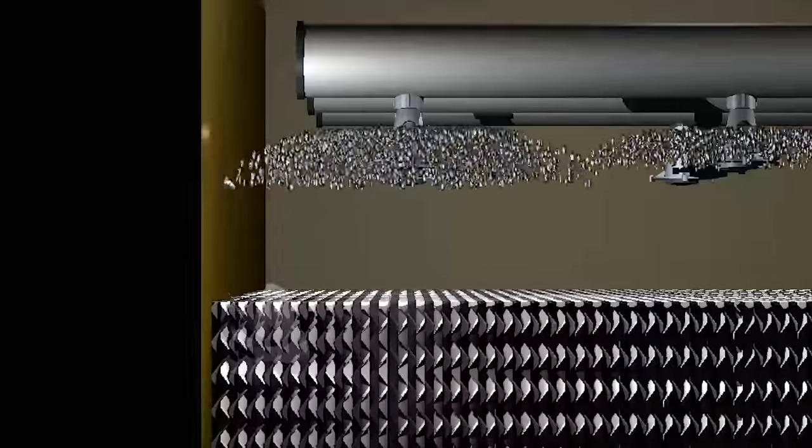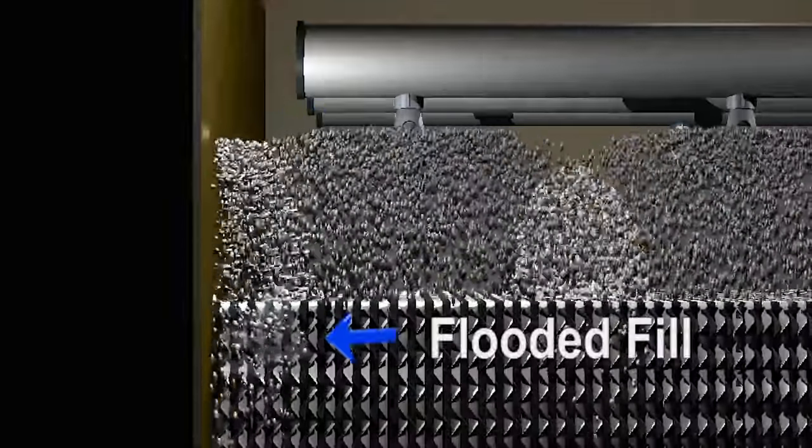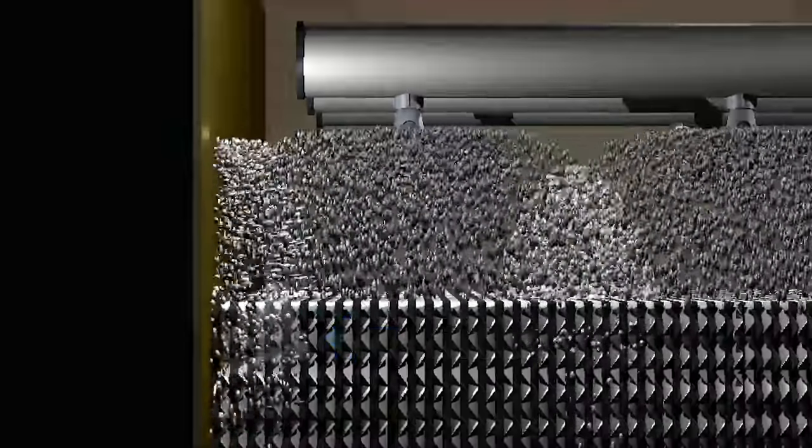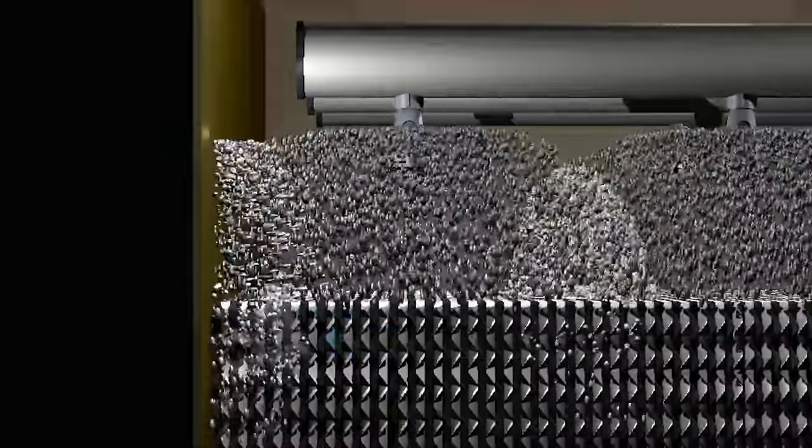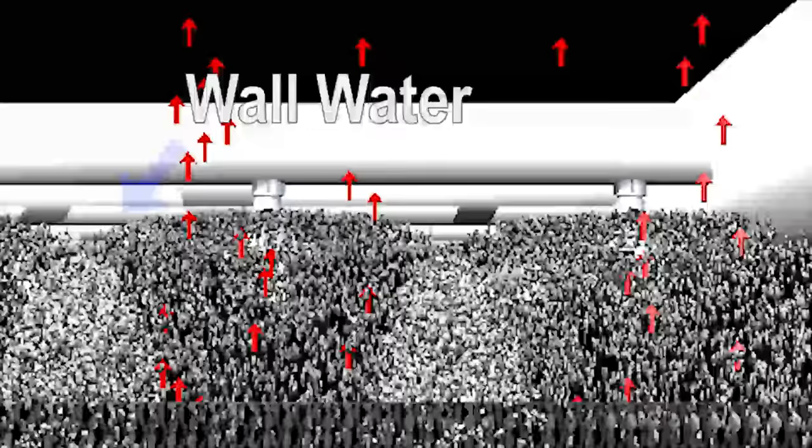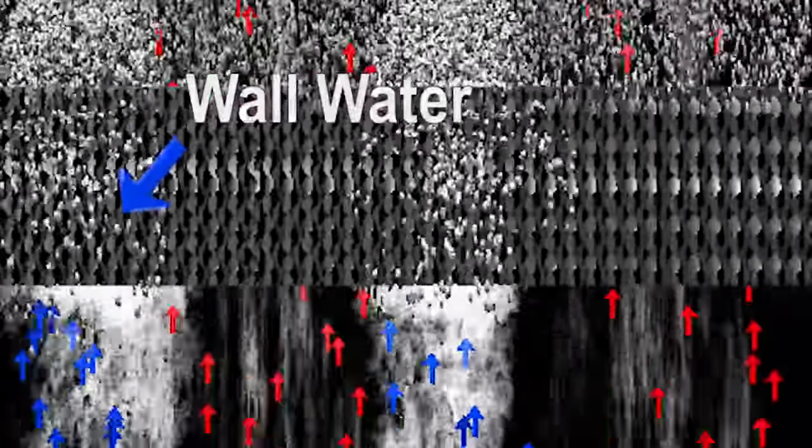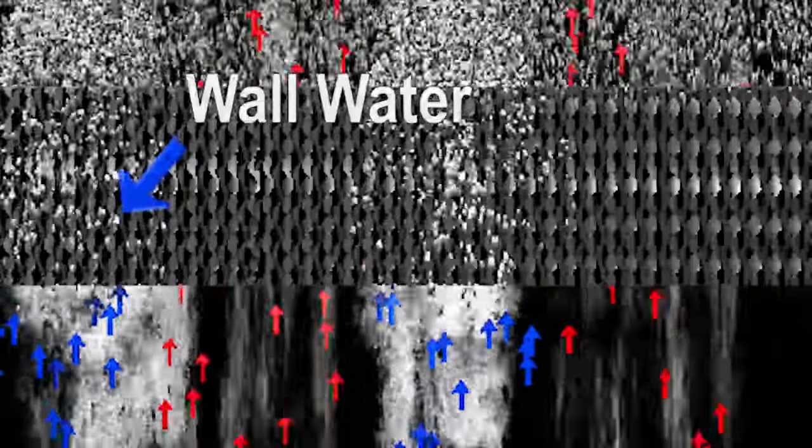The same circular water pattern of the spray nozzles hits the walls on the perimeter of the cooling tower, flooding the film media in these areas. So what's so bad about wall water? It had to be pumped to the top of the cooling tower. It flows down through the flooded areas of the film media, mixing with little to no airflow, and as a result, receiving poor heat transfer.